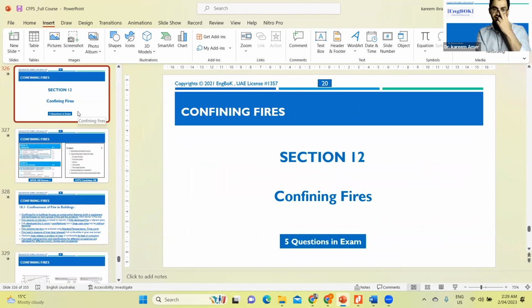Last section, number 12, confining fires. Here we mean how we confine the fire in order to provide safe evacuation. Maybe passively, maybe actively. Passively, by the construction itself, like, as we said, fire compartmentation, or the interior finish, or penetration sealing. Like if you have cable or pipe or duct penetrating, for example, a fire-rated wall or door, you should provide fire sealing or fire stop, or you should provide fire stop structurally during your slab or walling, between wall and slab, and between wall and roof or ceiling.